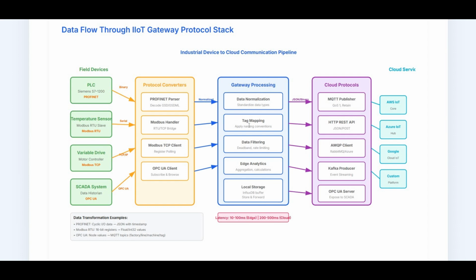Next comes gateway processing. Data normalization standardizes types and units. Tag mapping applies consistent naming conventions so data makes sense across systems. Data filtering removes noise and rate limits updates. Edge analytics aggregate values and perform calculations. Local storage buffers data using a time series database, so nothing is lost during outages.